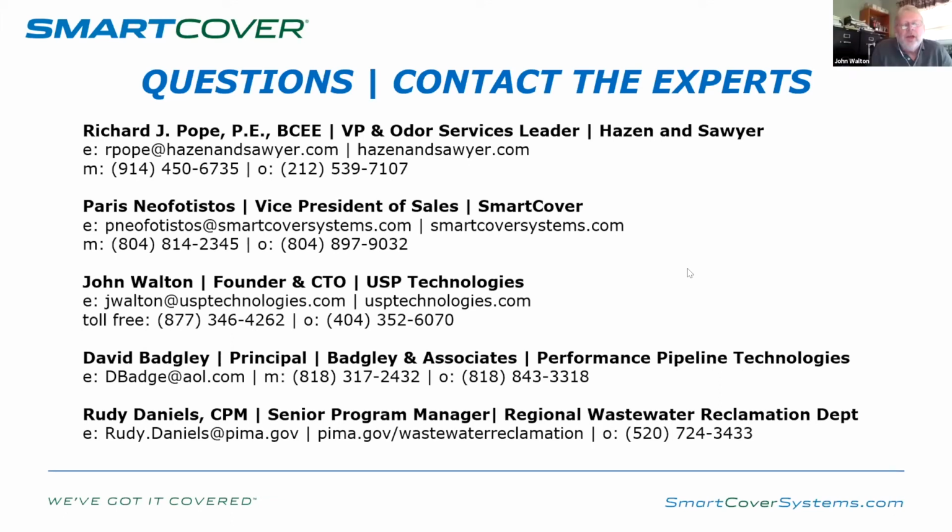It's John Walton. I would just add one more thing, and that's the use of vapor pressure measurements. They sit those in, and if they're just bouncing around zero, you have a fully breathing sewer, in and out. If you get numbers where you're building up a few inches of water pressure, that suggests you have something that's not circulating, and how representative is that H2S, and what does that number really mean in terms of controlling sulfide in the system?